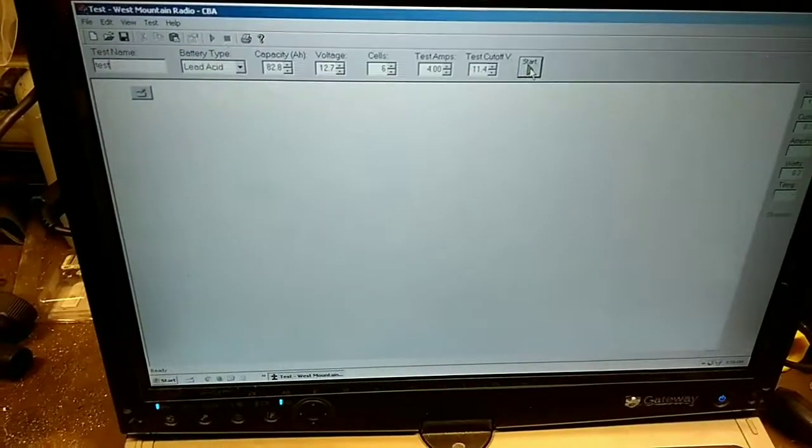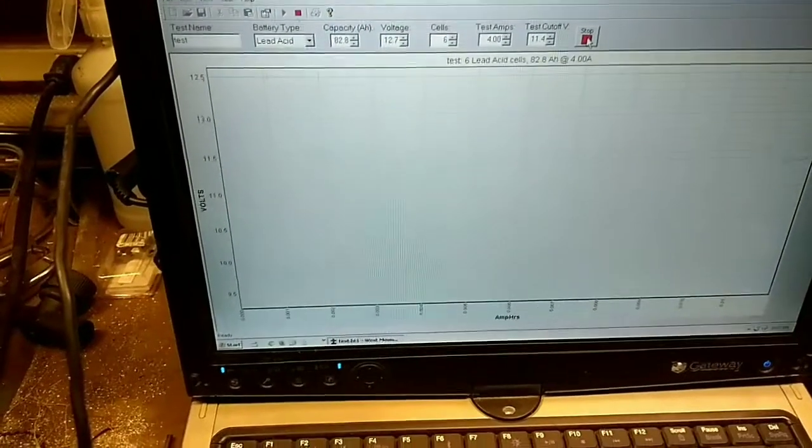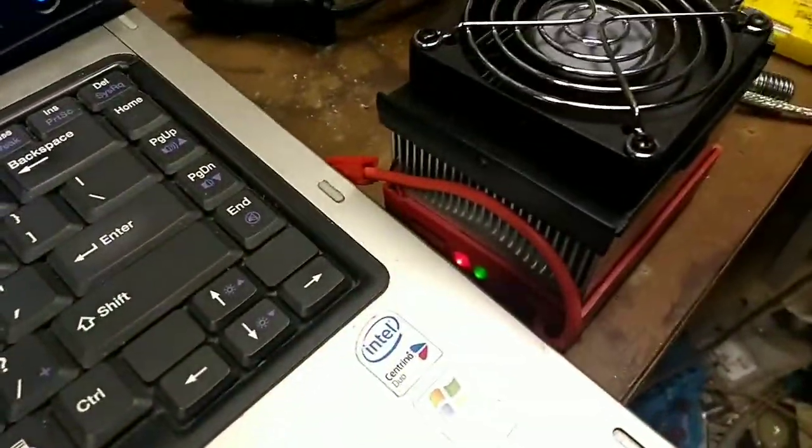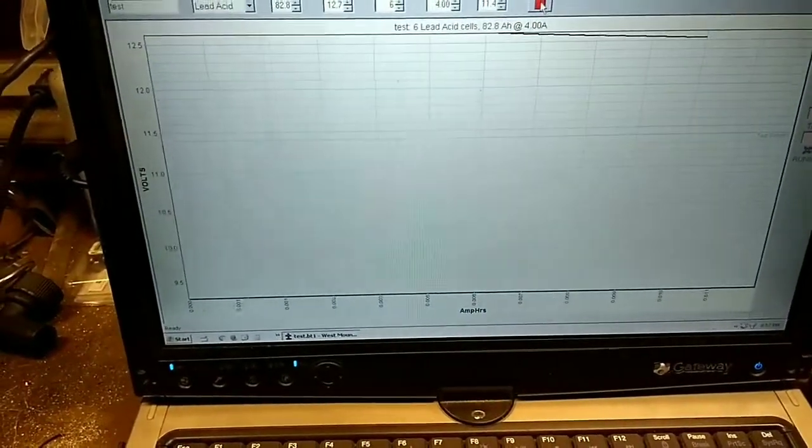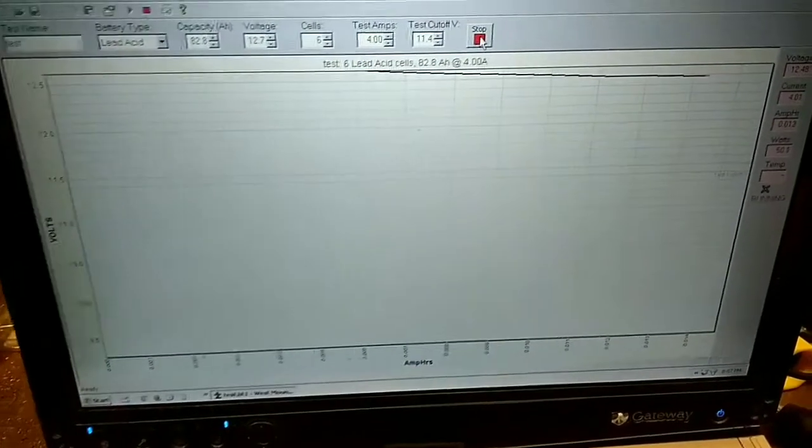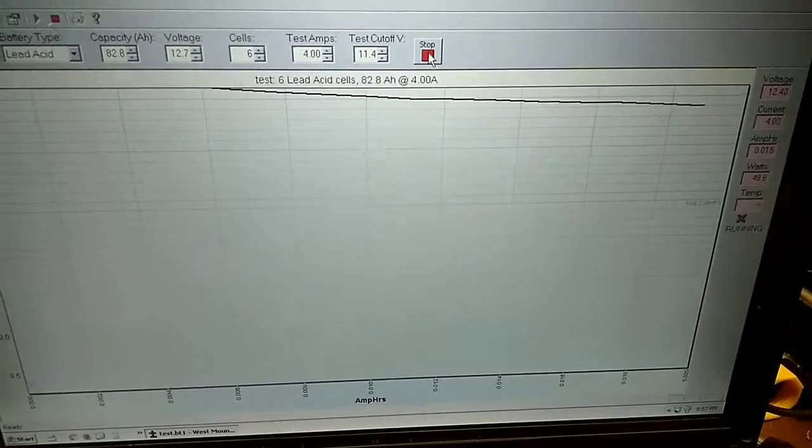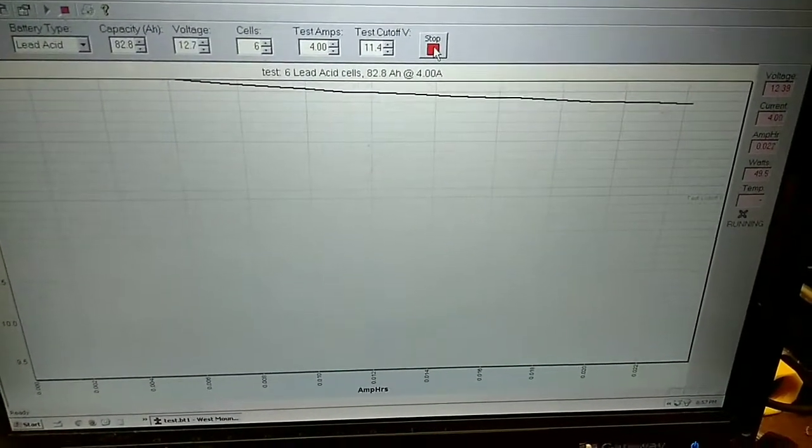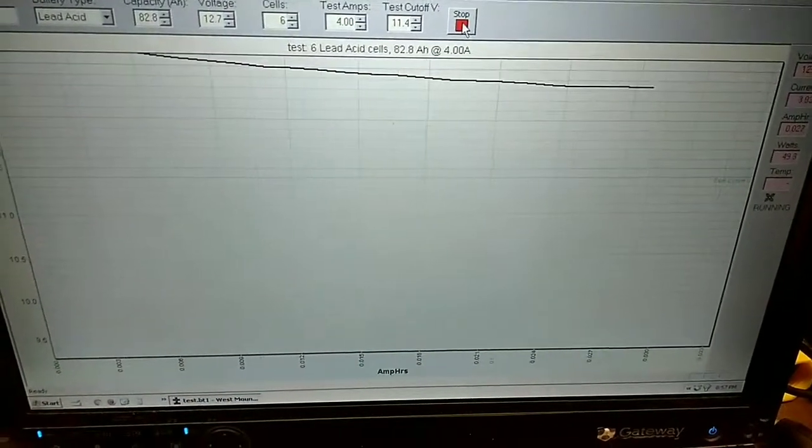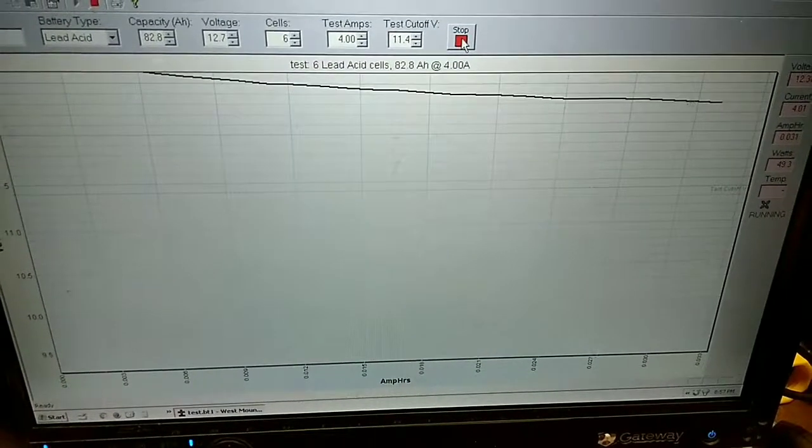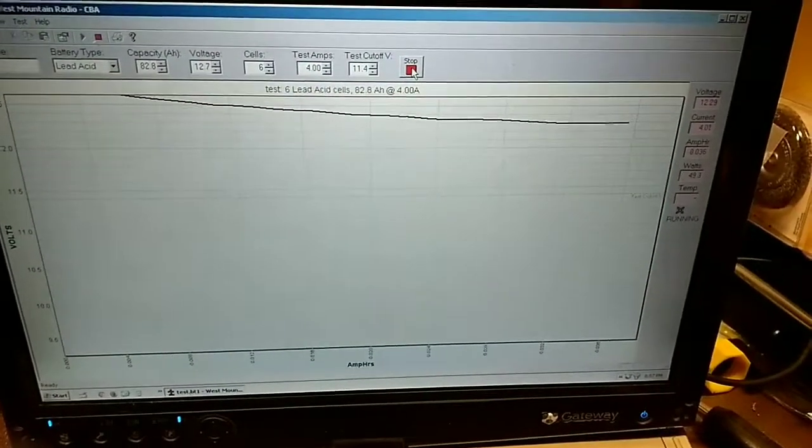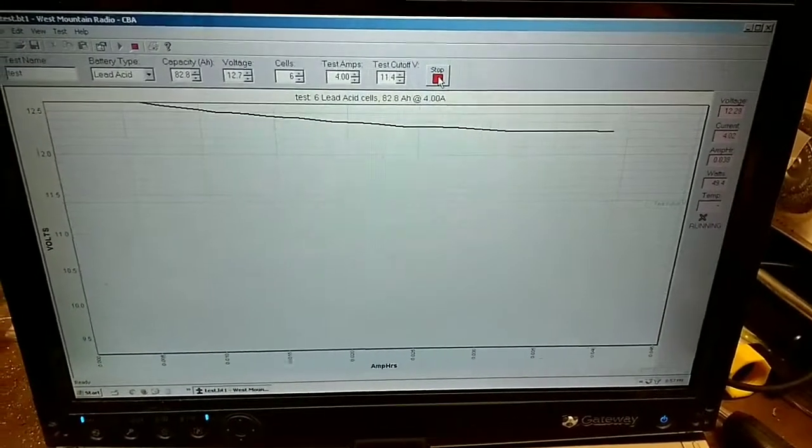Alright, computer kind of froze up but now I've got test in there and I believe I can push start. And there she goes. So the fan over here just started, my red light came on says that the thing is in fact testing. The current and it will graph the volts and current the whole way down. So you can see it's already starting to graph. Now the voltage dropped off pretty quick, little surprised by that. We may just have a bad battery.